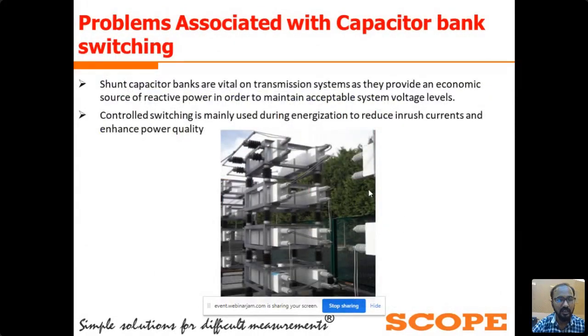Now we will see the control switching device application for capacitor bank switching. Same as with a power transformer, the main issue with shunt capacitor banks is also the high inrush current at the time of capacitor bank energization. Shunt capacitor banks are vital on the transmission system as they provide an economic source of reactive power in order to maintain acceptable system voltage level. We are using the capacitor banks in our power system for stabilization purposes, managing the reactive powers. We are majorly using the capacitor banks.